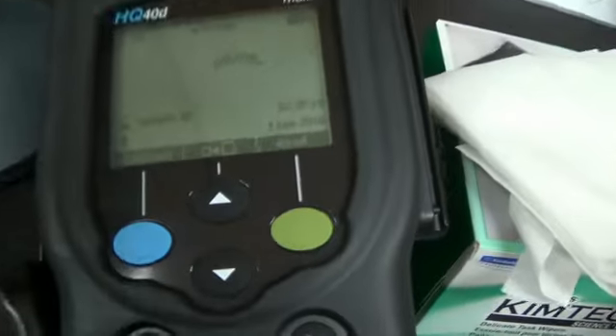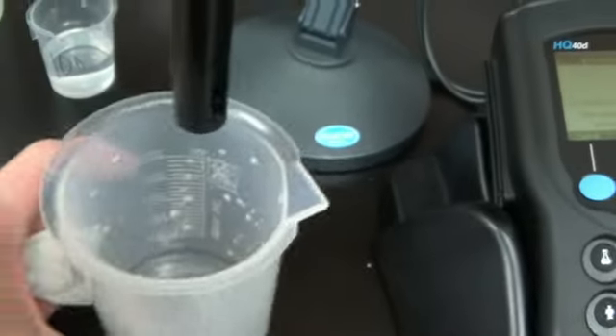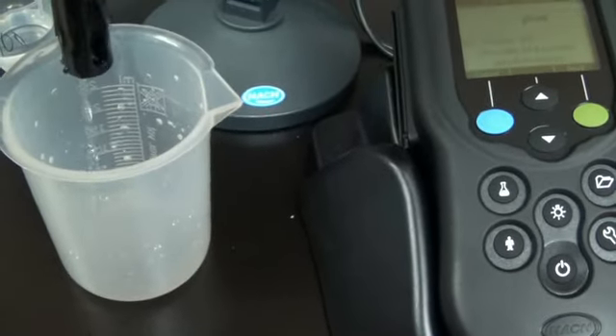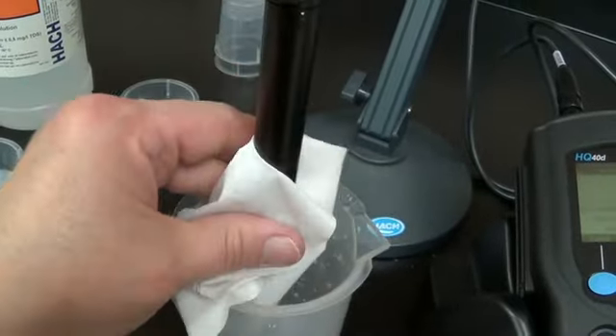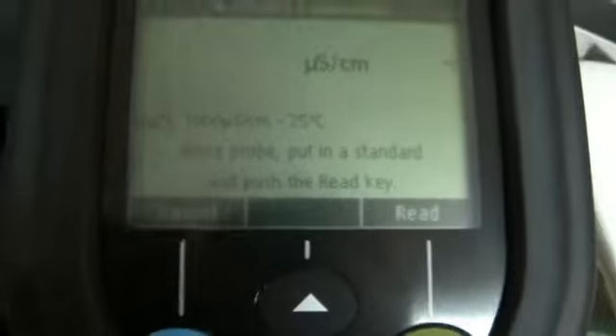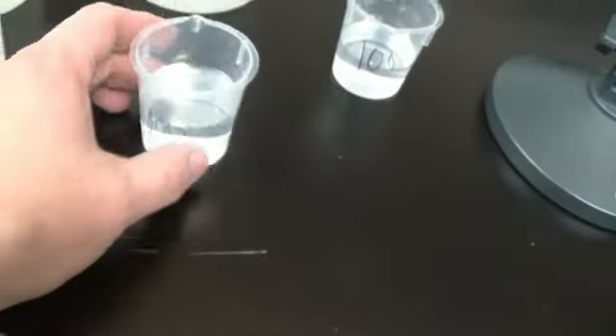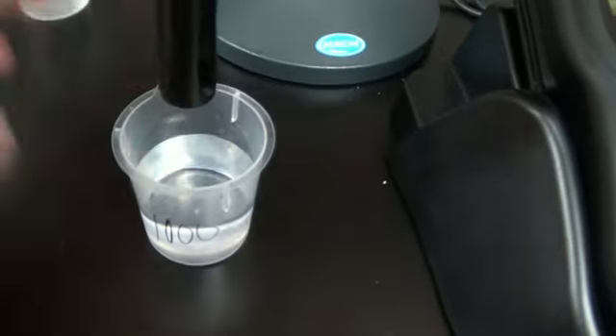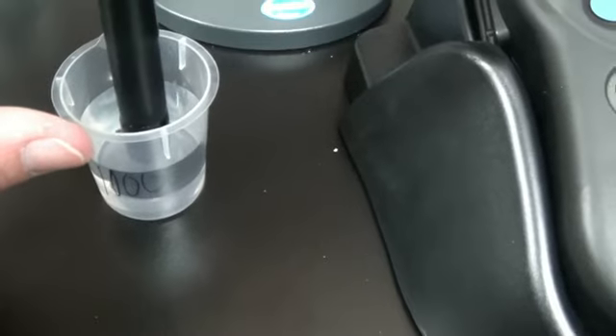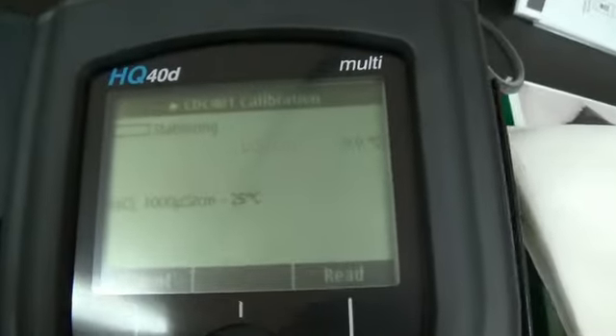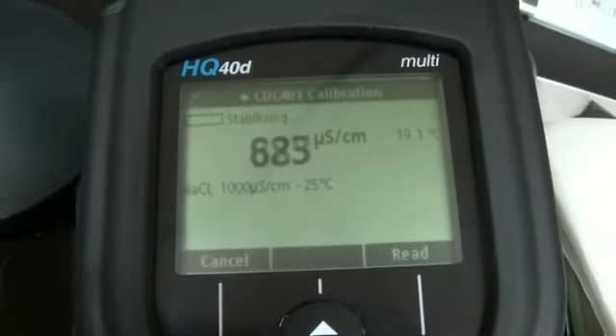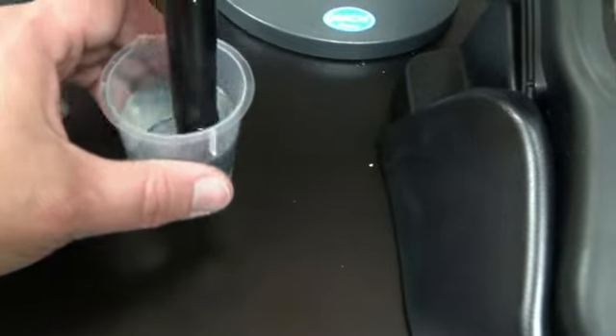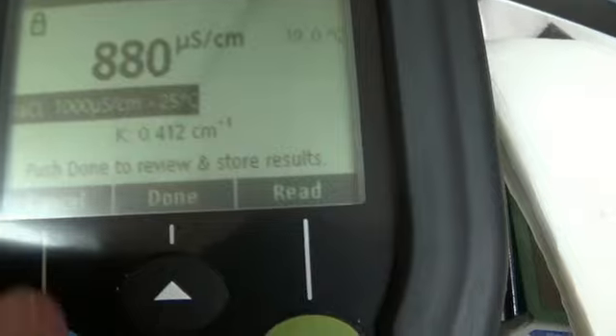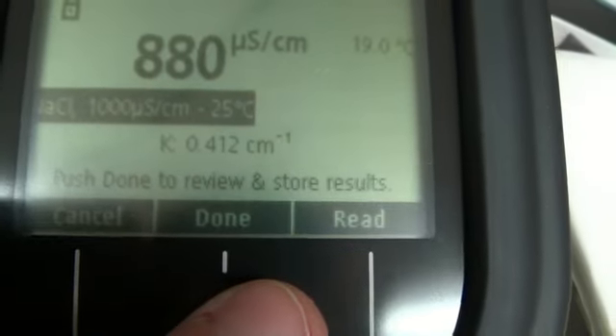So we are over here. We're going to calibrate it. So now I'm going to hit calibrate. I'm going to rinse off the conductivity probe. Here it says it wants you to start at 1000. Rinse probe, put in standard, and push the read key. So I have my 1000 here poured off. Press read. Stabilizing. While it's stabilizing. Alright, it is stabilized. It says push done to review and store results.